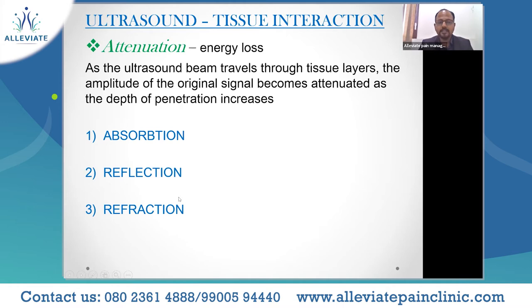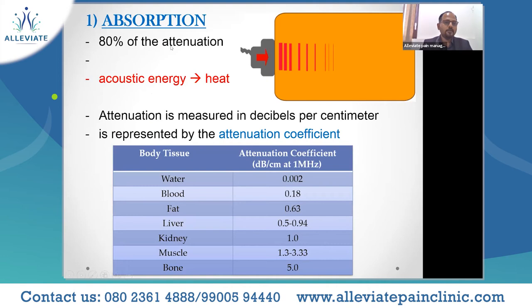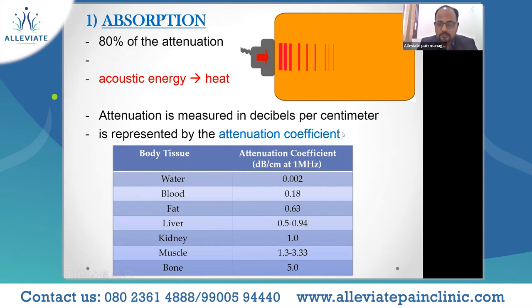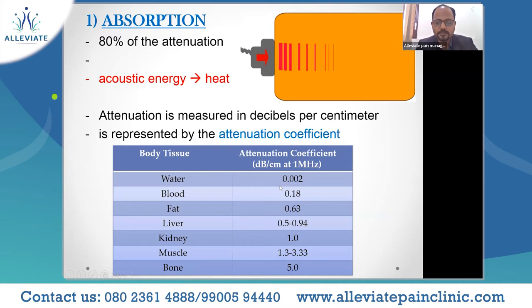More than 80% of attenuation is because of absorption. The ultrasound waves get sequentially absorbed by the tissues. This leads us to the attenuation coefficient — different tissues have different absorption capacities, measured as decibels per centimeter at one megahertz. Water has the lowest attenuation coefficient, and bone has the maximum attenuation coefficient. This is why in a water phantom at workshops, you are able to see structures very well — there is very little absorption of ultrasound waves in water.